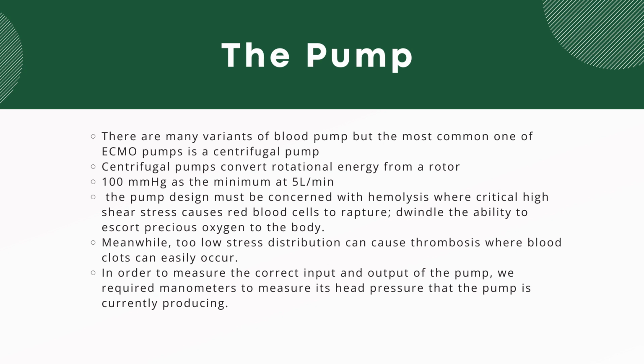Keep in mind that the pump design must be concerned with hemolysis, where critical high shear stress causes red blood cells to rupture, losing the ability to escort the precious oxygen to the body. In some cases, if the hemolysis rate is off the charts, the patient will die.